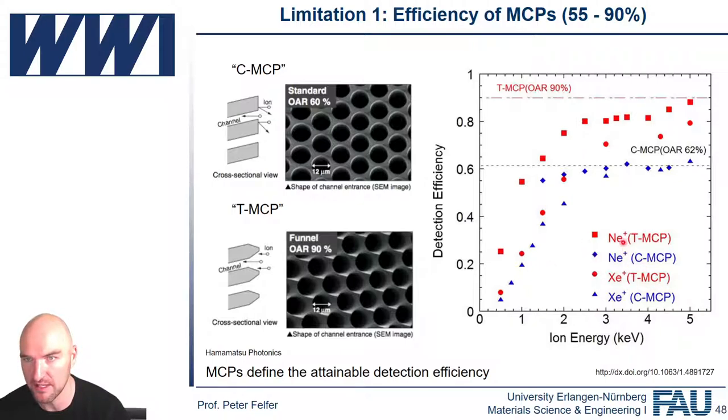experiment with xenon and neon ions for those funnel shape MCPs is really only reached at 3 kV plus, and the full saturation at about 5 kV. So you've got the plateau between about 2.5 and 4 kV, and then the full saturation at about 5 kV.